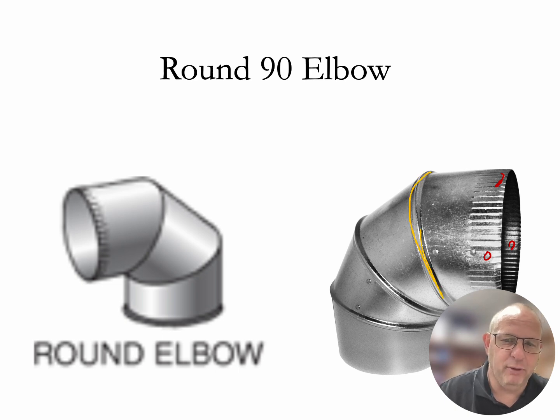So any place where air can come out. And these joints right here are pretty notorious for moving air out of them. So we'll take our mastic after we have put this pipe in place, and we will seal up every aspect of that pipe. If we were insulating it, we would wrap it in our foil back insulation with our fiberglass to give us even more R value for our metal pipe itself.